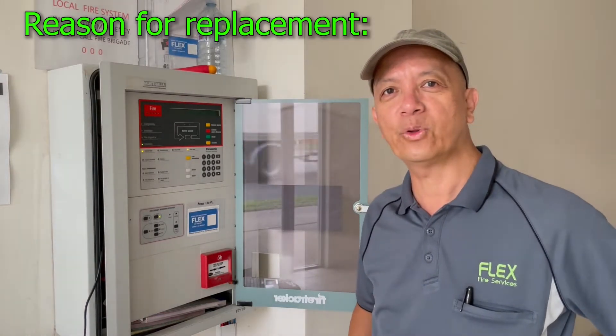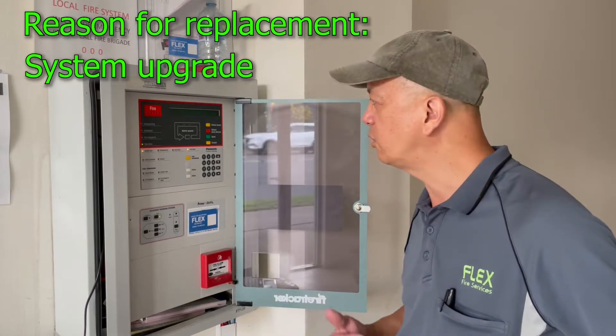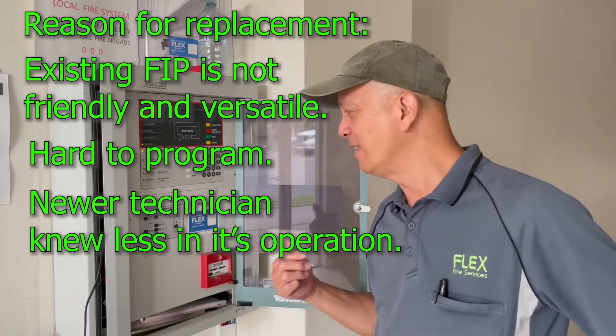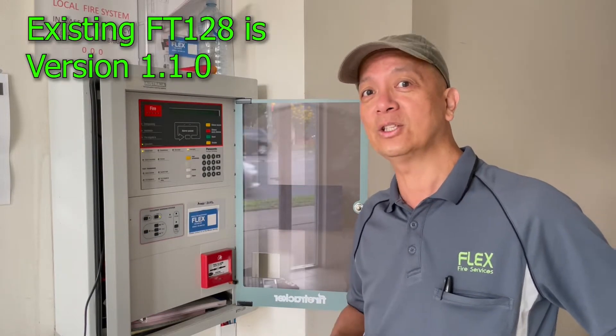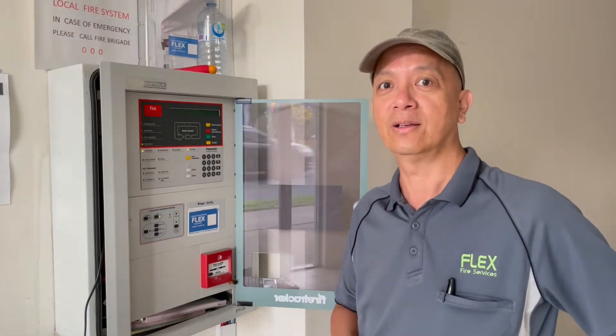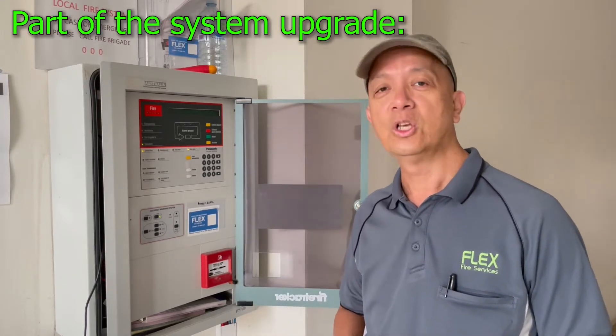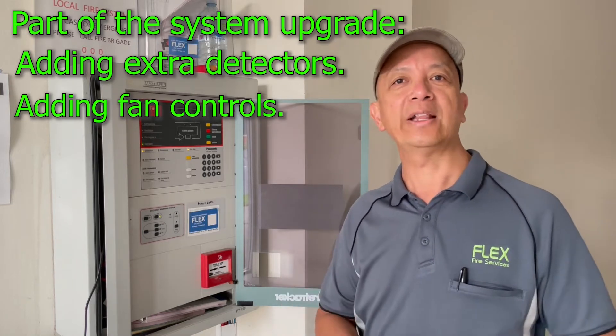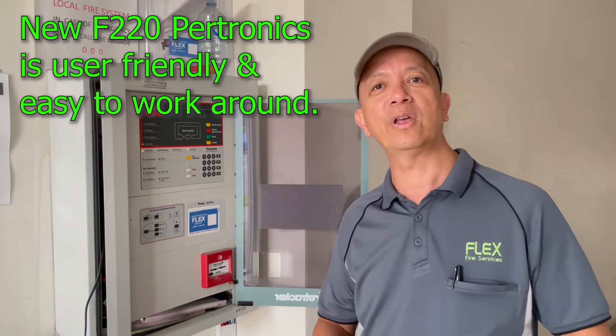Why are we replacing a FT128? The main objective here is to make the system updated. It's very hard to program this system if you are not a senior technician or a good programmer. It's not a friendly system, it's not even a versatile system. The new Pertronics that I am always installing are versatile and very user-friendly. We are going to install extra detectors in this building, so I suggested to my customer that this fire panel must go. Any technician will be aware of the new fire panel — they can program it, they can do anything they want because the F220 Pertronics is user-friendly.